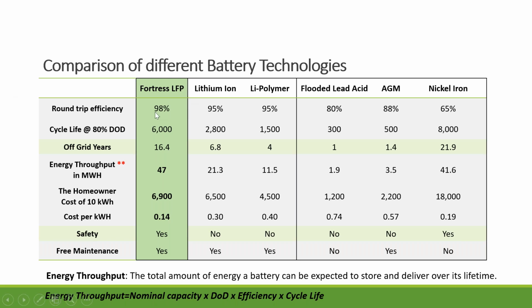The LFP has 98% round trip efficiency. The other lithium batteries about 95%. Flooded lead acid is 80%, AGM is 88%. Nickel iron is much less, only 65%.